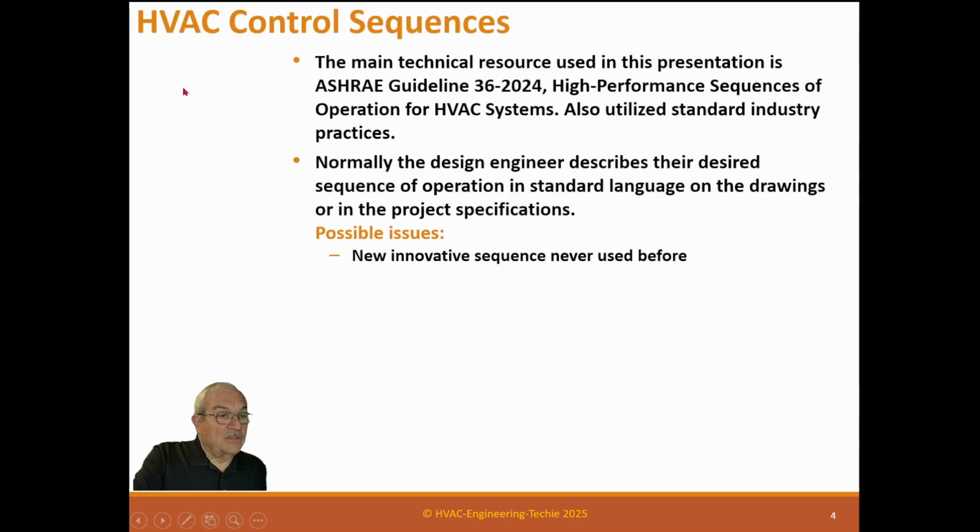I always tell a young engineer, I know you're smart, but if you're going to create something no one's ever seen before in the HVAC industry, then you need to put enough money in your project to be able to train everybody on what it is and how it works. And that includes the owner and his operators, the control contractor, the programmer, the commissioner, the test and balance guy, and the contractor that's installing it. If you do not do that, it will not work. It will fail somewhere along the line because someone doesn't really understand what's going on, and they'll apply something they've done in the past from a standard system, and it won't work.